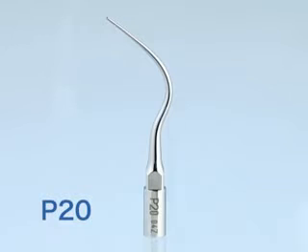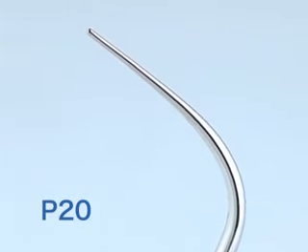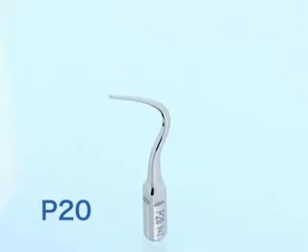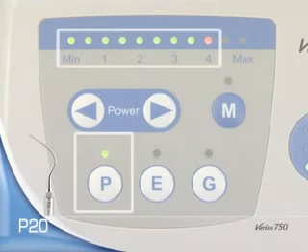Tip P20 is used with Varios 750. Lower power should be selected for fine tips. High power can be dangerous and should be avoided as it may cause fracture of the tip.